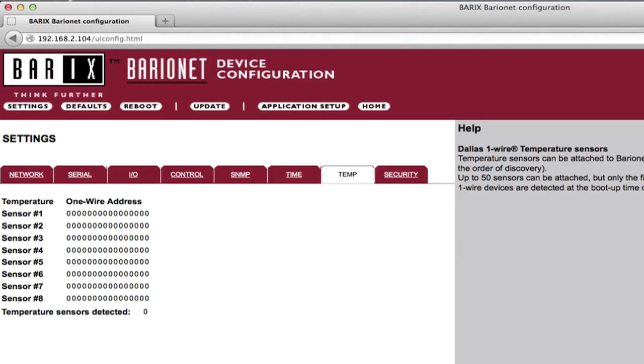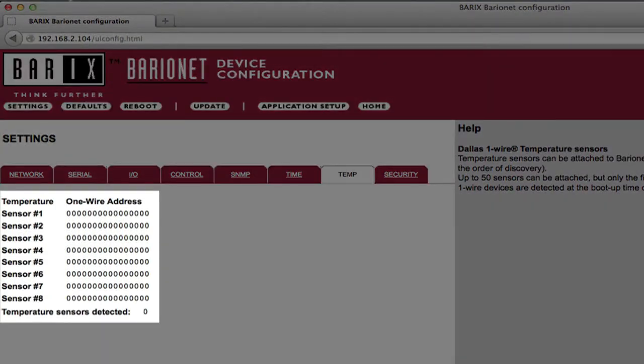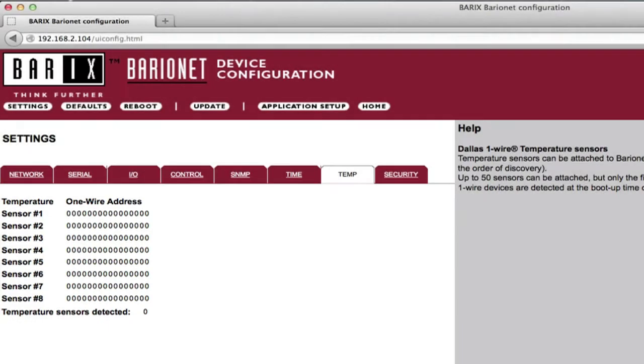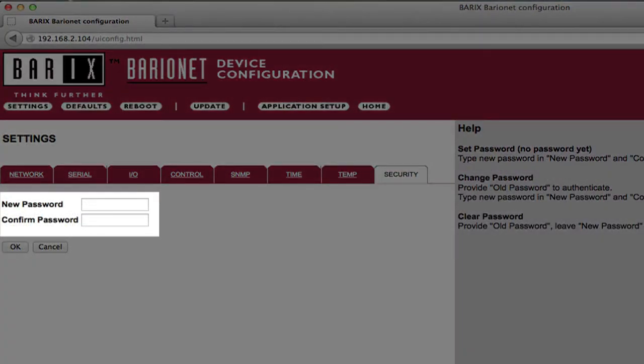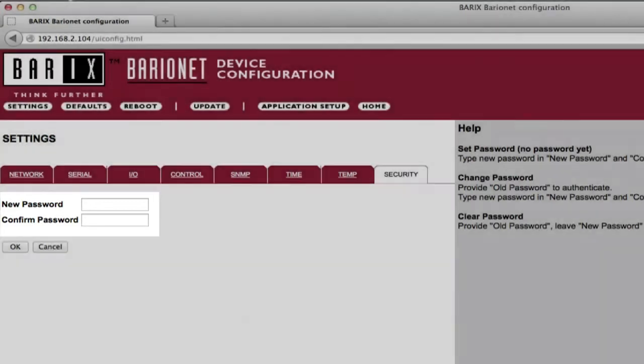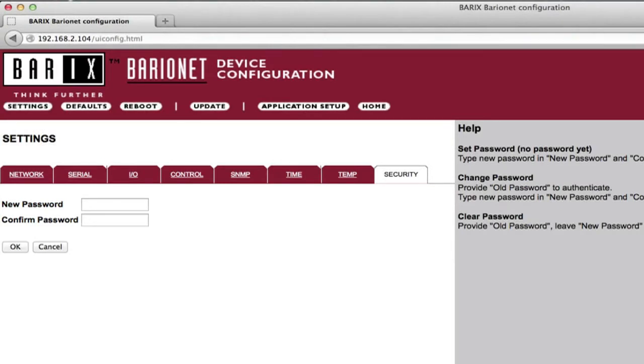The Temperature Settings page shows the unique hardware IDs of the first 8 temperature sensors detected on the one-wire bus. Up to 50 temperature sensors can be supported by the Barionet, but the hardware IDs of only the first 8 are displayed on this page. The Security page allows setup of a password that can be used to protect the configuration pages, as well as any custom HTML pages installed on the device. By default, no password is required for access to the configuration pages.